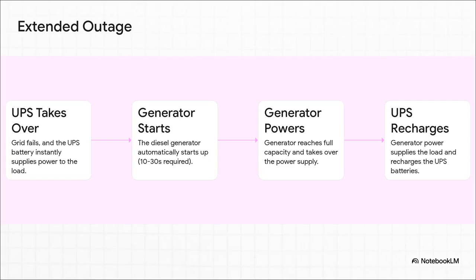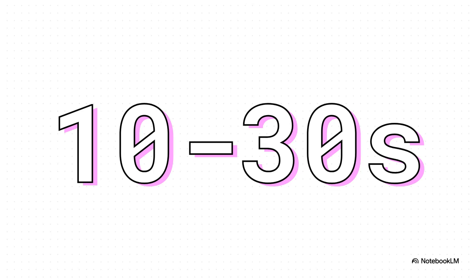It's incredible. Okay, now for the main event, a total grid failure. The moment the grid goes down, our sprinter, the UPS, instantly takes the load, just like it did before. But at the exact same time, it sends a signal to our marathon runner, the diesel generator, to start up. The generator just roars to life, and once it's running at full, stable power, the system smoothly transfers the load from the UPS over to the generator. And this just brilliantly shows you the crucial role of the UPS. That whole startup sequence for that massive generator takes about 10 to 30 seconds. That's the critical gap. The UPS's entire job in this whole scenario is just to sprint for about half a minute, perfectly bridging that gap to ensure the power never, ever stops.